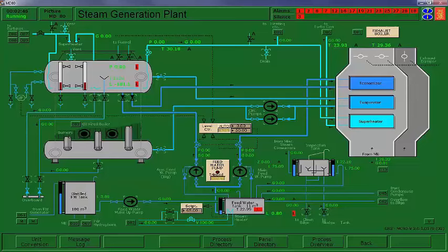And I'm going to start filling the feed water tank. This is too low, and we're going to fill that to above 1 meter. So we'll start that up. While I'm here too, I'm also going to open up the steam valve to the feed water tank. Again, we're lining up systems ready to go. So we want the small one, and you see down here, the upper one is the small. We need to open up our feed stops, both the main and the auxiliary.